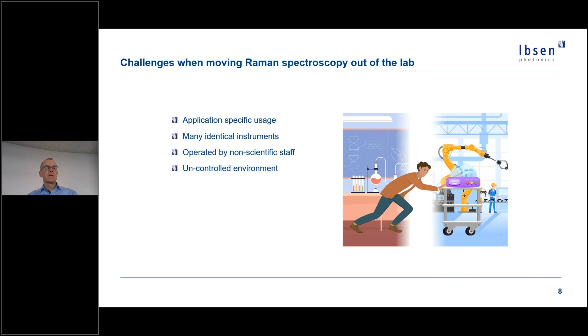When Raman spectrometers are used outside the lab, the situation changes completely. In industrial environments, Raman spectrometers are typically used for a very specific application where a large amount of similar, known types of samples are analyzed in a continuous stream. This requires many similar instruments that ideally should provide the same result, no matter which instrument a given sample is measured on. Two other big differences to the lab case are that the operators are non-scientific and the environment is uncontrolled, meaning that, for example, temperature and humidity may vary quite a lot.